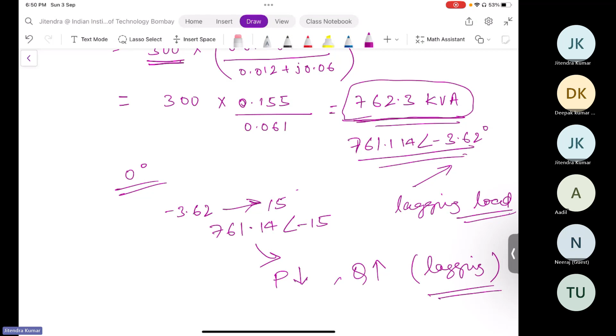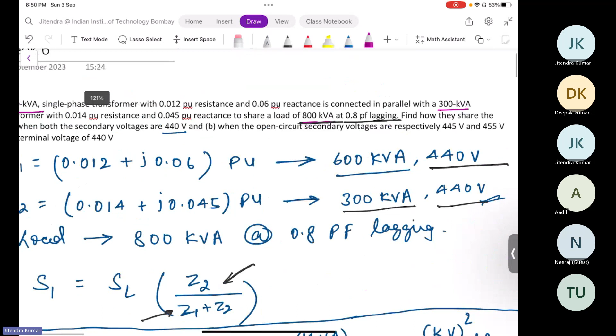So even though the sum of the ratings of the two transformers was 900 kVA, we end up overloading one of the transformers. This has happened. Why? Could you please let me know why this has happened? In fact, the sum of both transformer ratings was 600 kVA plus 300 kVA, that is 900 kVA, and we have load of only 800 kVA. In spite of having higher kVA rating from the source side, we end up overloading one of the transformers. Why did it happen?